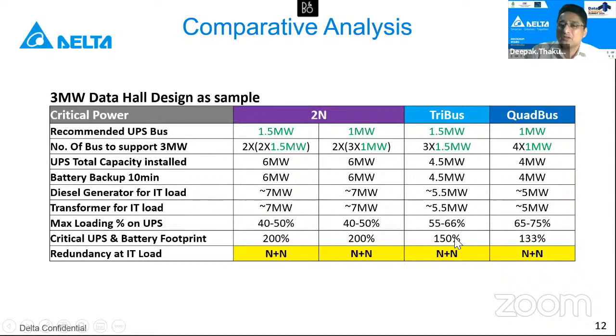Space saved is almost, you can say, around 25 to 30 to 40% by adopting a tri-bus architecture, which means an additional rack capacity can be deployed when you design a new one. Or with an existing facility, you can actually create more output with a tri-bus architecture and make it a much larger IT data center than it is currently. And with the quad bus, you can simply see again, the same concept, 2N is achieved with four numbers of 1 megawatt. That means with 4 megawatt of installed UPS capacity, you can achieve a 2N architecture design, and with 4 megawatt of battery.